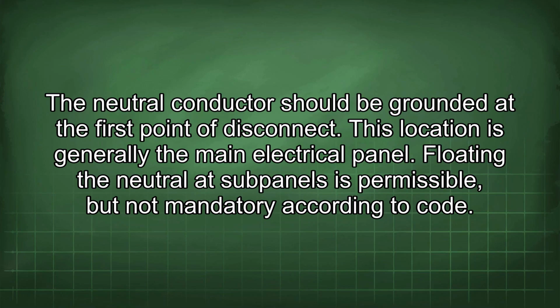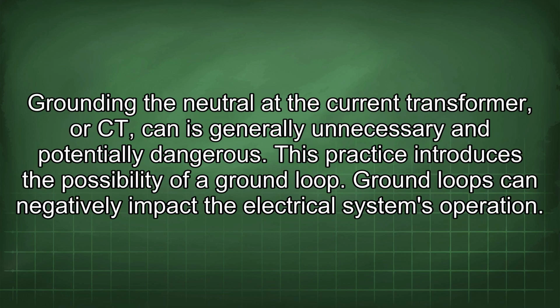The neutral conductor should be grounded at the first point of disconnect. This location is generally the main electrical panel. Floating the neutral at subpanels is permissible, but not mandatory according to code. Grounding the neutral at the current transformer, or CT, is generally unnecessary and potentially dangerous.